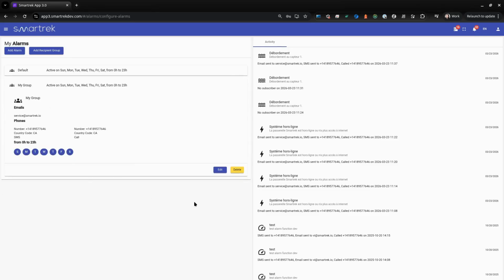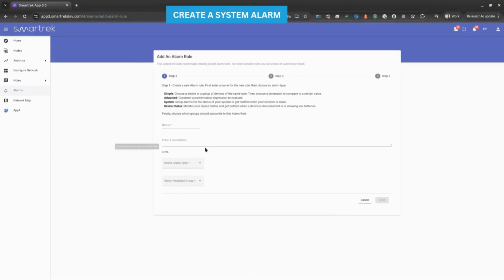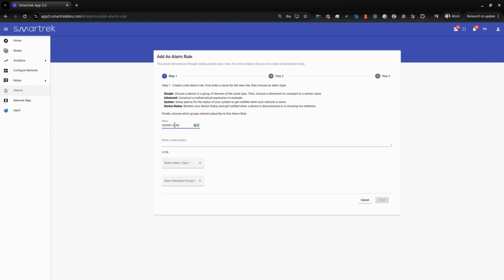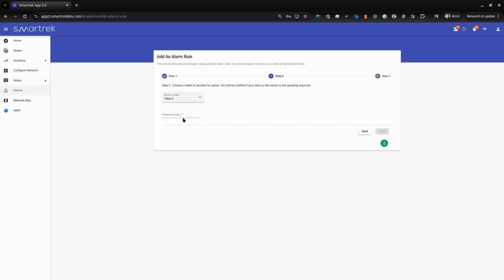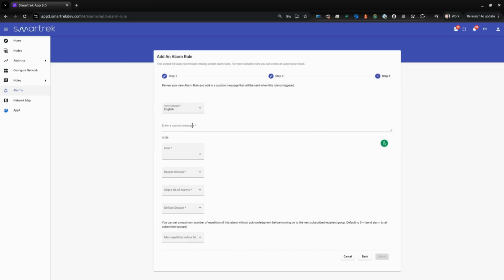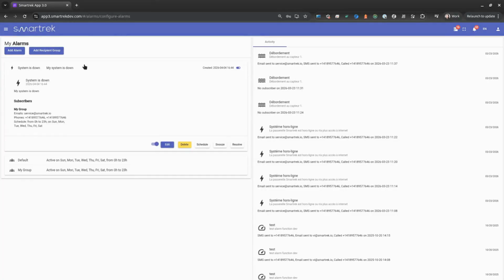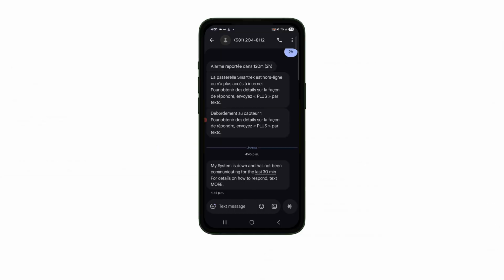Next, create a system alarm to be notified when the gateway loses communication with the servers. Name your alarm, enter a description, then select the system alarm type. Then select your subscriber group. Choose the table corresponding to your system, then enter a delay of 30 minutes. Enter the text you'd like to receive. Then configure the following options. Set a repeat interval of 5 minutes, don't ignore any alarms, and set an automatic rearm time of 5 minutes. Your alarm is now created and will send you an alert if your gateway loses its connection to the servers for more than 30 minutes.